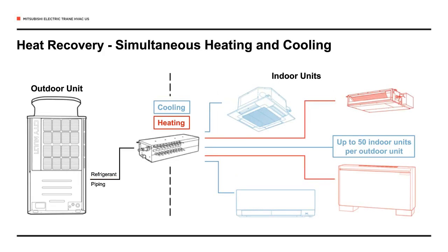Heat recovery VRF systems, on the other hand, offer cooling and heating simultaneously within the same system. As mentioned earlier, VRF systems with heat recovery are the ideal choice for office buildings, hotels, and any facility with diverse comfort needs that might require some zones to be heated while others are cooled. One example of that might be an office building that gets a lot of morning sunshine. In that example, some of the areas of the building might need to be cooled, whereas if the other side were still in the shade, those areas of that building might need to be heated, for example.